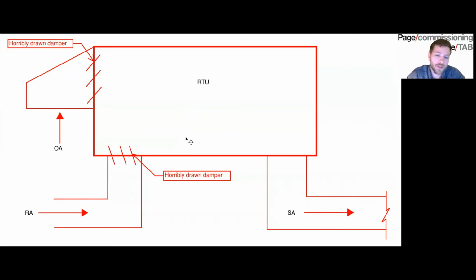Now, again, the method that I've been talking about won't work in all situations. Sometimes you don't even have a return air damper, and there's no real way to reach the return air to where you can fully block it off. And so when you reach that situation, your only option really is to do a velgrid reading at the inlet to the outside air, or potentially you could use an anemometer if you trust that device better. Some people use a hot wire. You can use whichever device you're comfortable with.